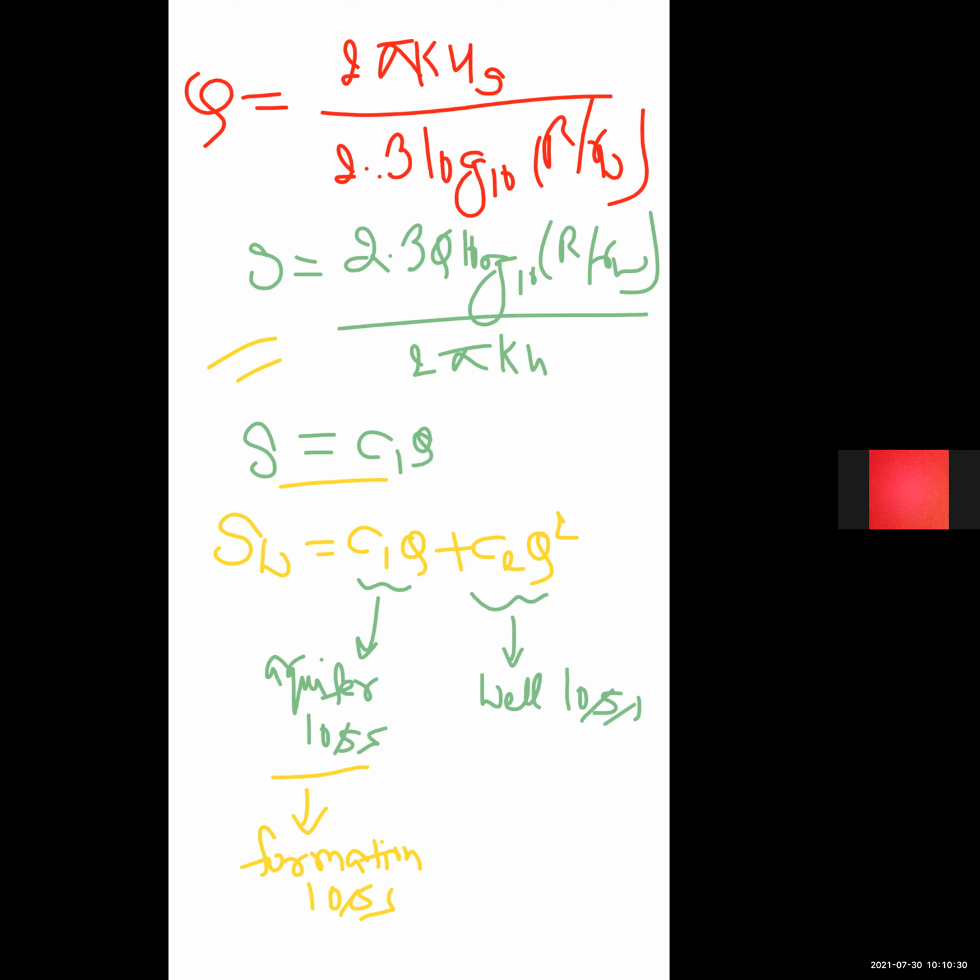In case of an unclogged or undamaged well screen, where the screen size is compatible to the surrounding porous media, the well loss is mainly caused by the axial movement inside the well up to the pump intake, because the well loss caused by water entering the well through the screen is very small. When clogging of the screen increases, the well loss increases, which adversely affects the pump efficiency.